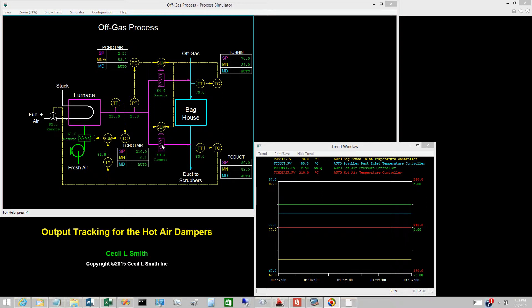If only one of the hot air dampers is on local, then the hot air pressure can be controlled using the other damper. To do this, the baghouse inlet temperature controller must be tracking if either hot air damper is on local.